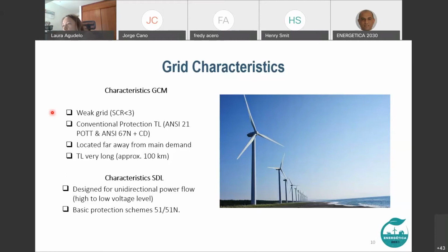Most of the protection schemes are conventional, based on distance and directional overcurrent. This is very important because this area is far away from the main demand centers. It is located in the north of Colombia, and most of the transmission lines in this area are long, approximately 100 kilometers.